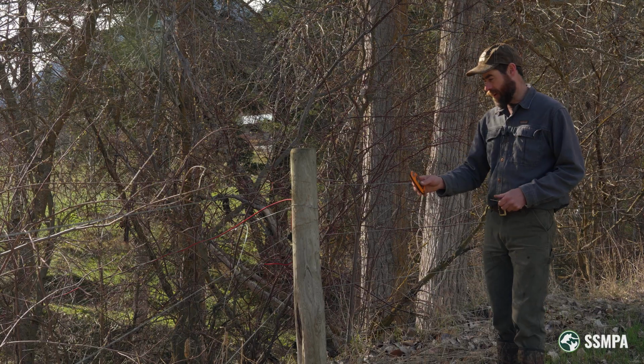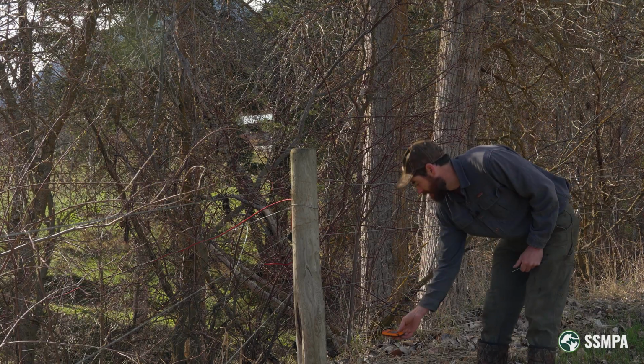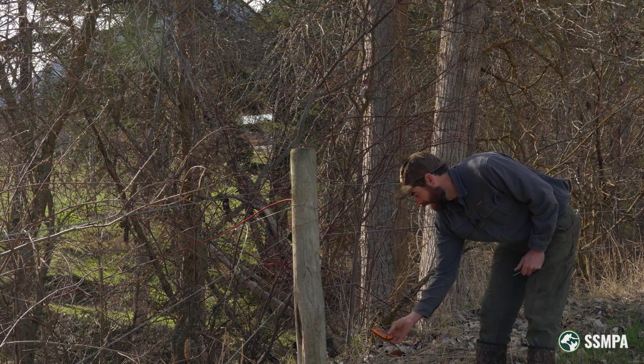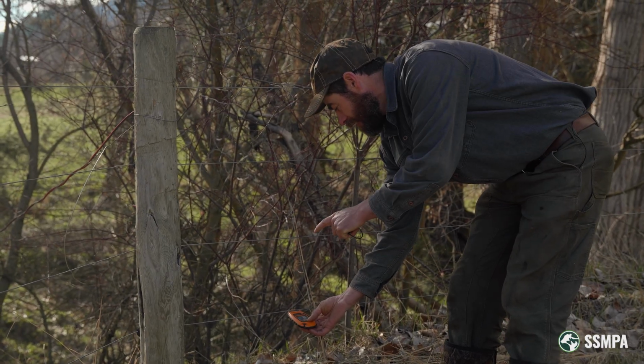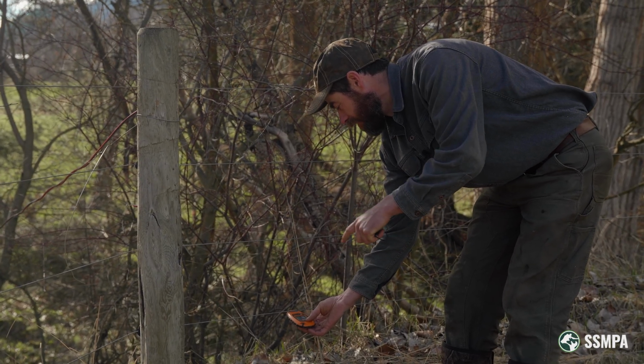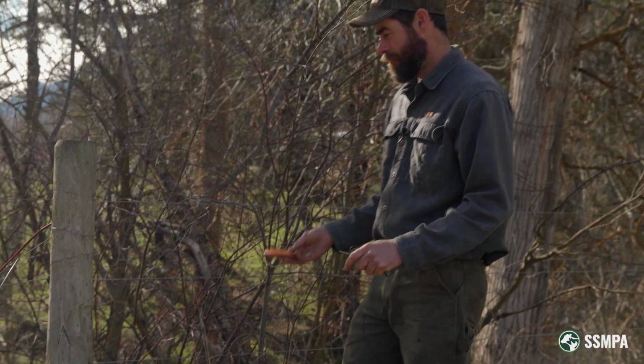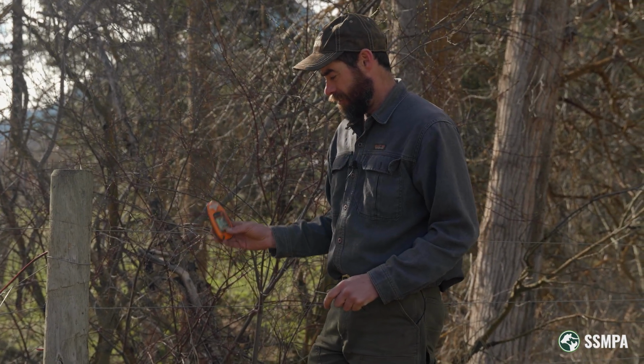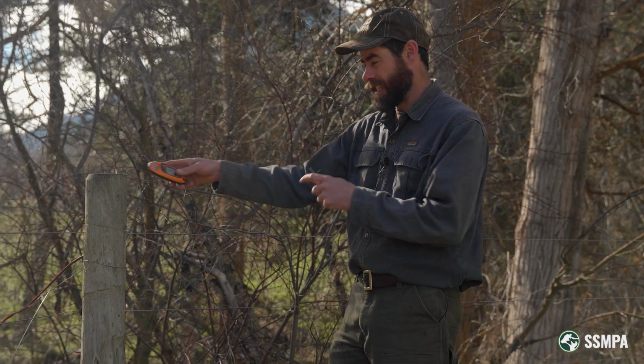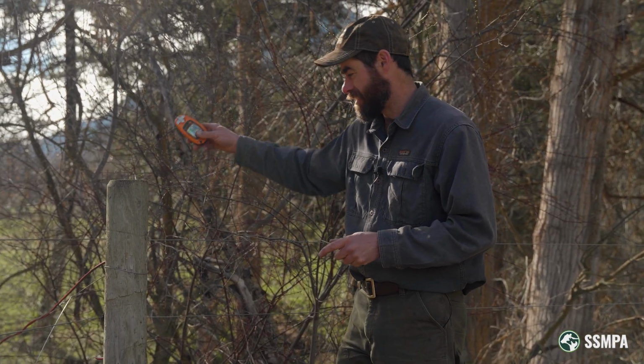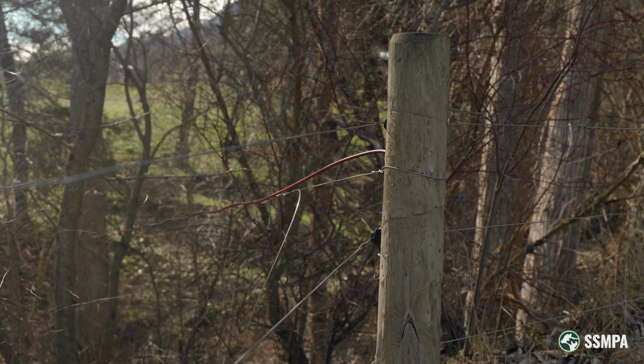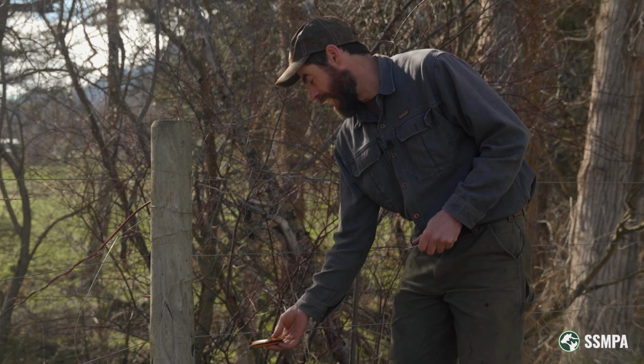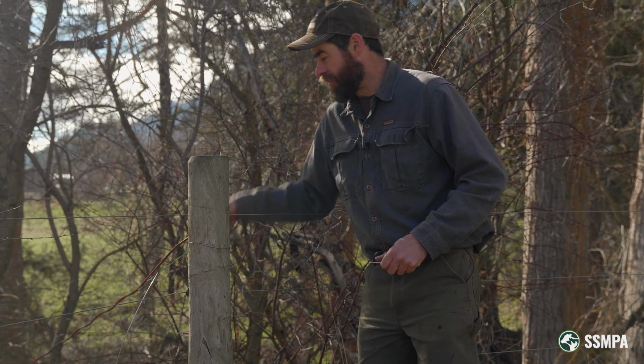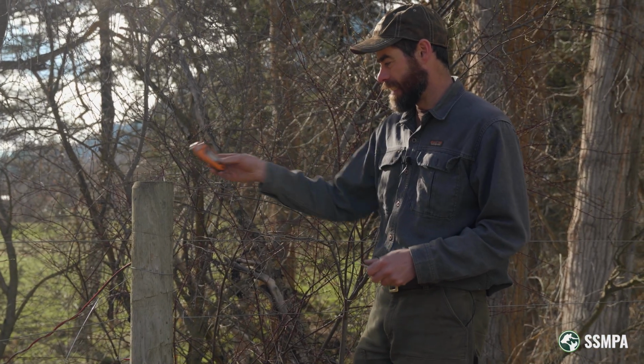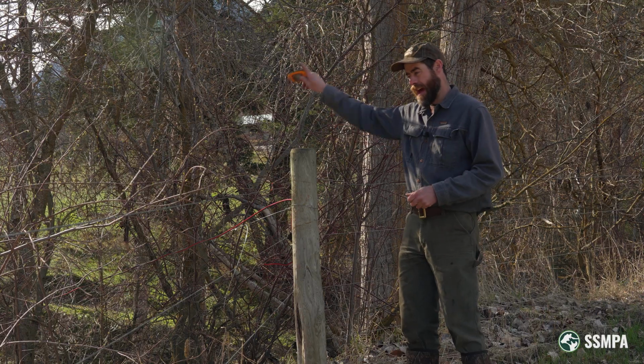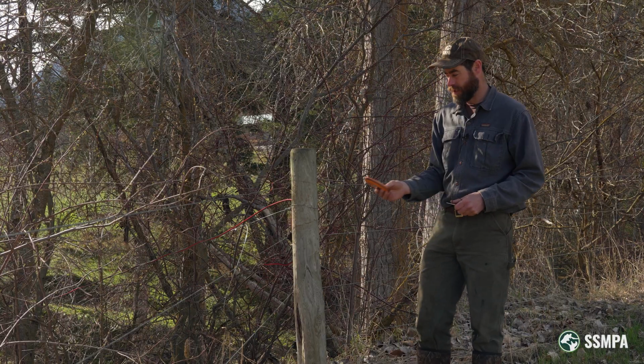We're going to continue down our fence line in the direction that the current is flowing, and we can see here we're down to around 2.8 kilovolts, and we've still got about 5 amps flowing this way. We definitely want to check the fence at each intersection. So if you have another fence taking off this direction that's taking its power from this fence, you're going to want to go to that spot and check the hot wires on both sides of the junction, right? Because that's going to tell you if the short is on that fence line or this fence line continuing down.